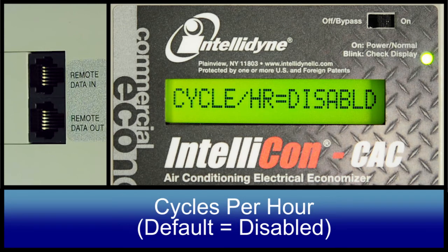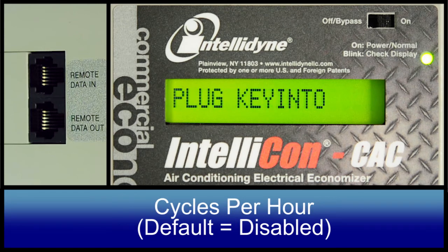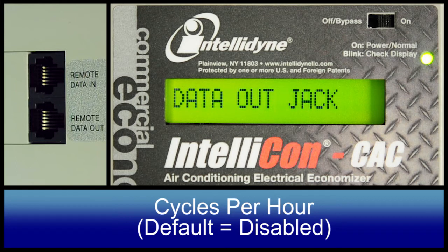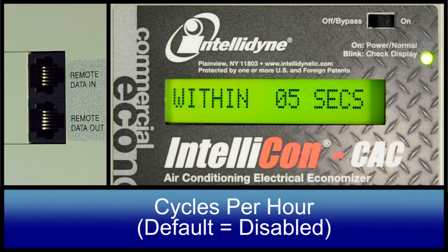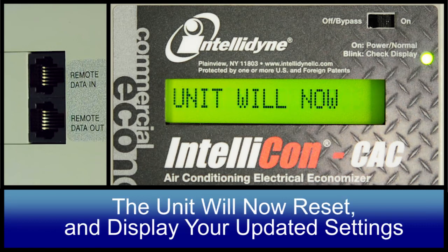Cycles per hour. This parameter causes the controller to force the compressor off after the desired continuous runtime for that cycle has been satisfied. The default value is disabled.